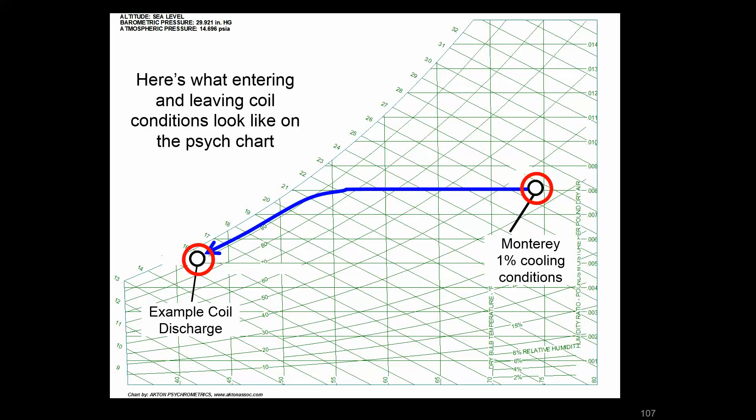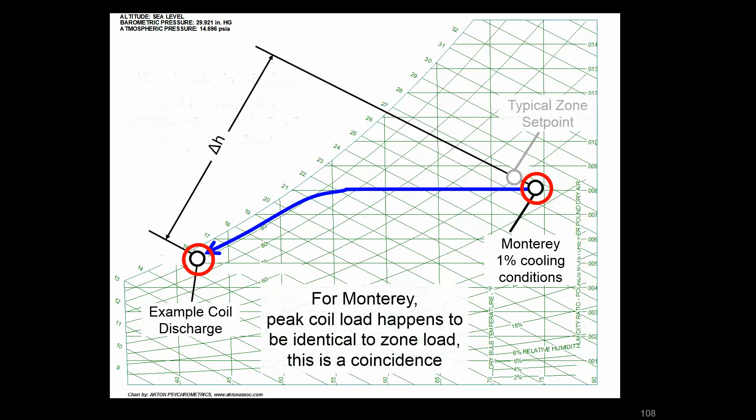So we can really look at a different process on this chart, which is not just the zone load process, but a cooling process. And that's going to be from this outside air condition. In this case, we're looking at Monterey, California's 1% cooling, which is a fairly mild 74 degrees at a little over 40% relative humidity. And we're going to look at what it takes to cool that down to the coil discharge temperature. So accounting for some bypass coil factor, what that delta H is that's going to be between the outside air and what's coming out of the coil. So the input to the coil and the output.